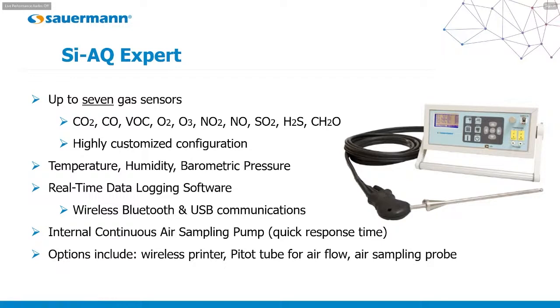That would be for if you want to measure air quality from a very precise location. In that case, you attach one end of the hose to the instrument, and the other end of the hose has the stainless steel probe. Then you just position the probe tip to exactly where you want to measure from. For example, that could come in handy if you want to measure from either the supply or return air going into a room. If there's a metal grill or a vent, you can stick it in there. If you want to actually measure the air quality within a flue or a duct, and you have a hole or a way to insert the probe inside, that allows you to measure a very precise location if you choose to. Otherwise, it's fine to use it without the probe. You'll just be measuring the general air within whatever space you're at for the indoor location.